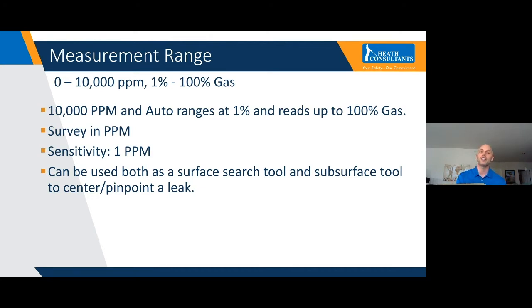It's all done automatically. If you're out doing a survey and you get an indication that goes into the percent gas range, it will automatically switch over. At 10,000 parts per million, or 1% gas, it switches over and starts giving you a percent gas and air scale. Because of this, it's a very versatile instrument. It can be used as both a surface sampling instrument and a subsurface instrument, to center and pinpoint a leak, or even to venture inside of a building if you need to.